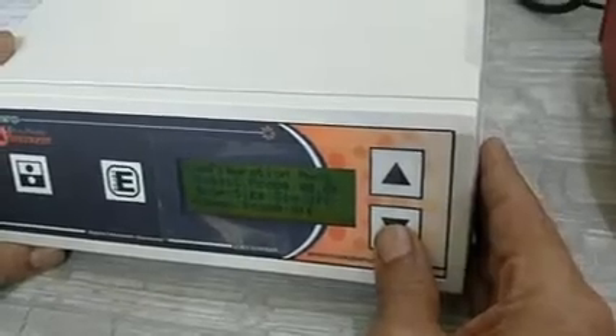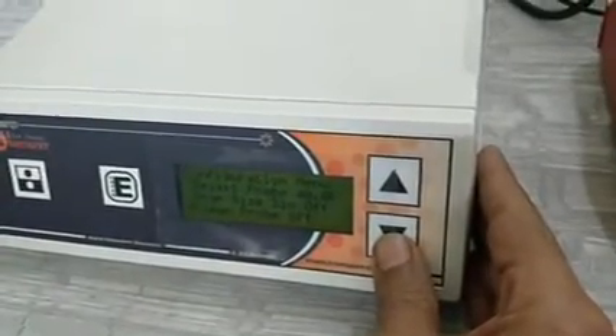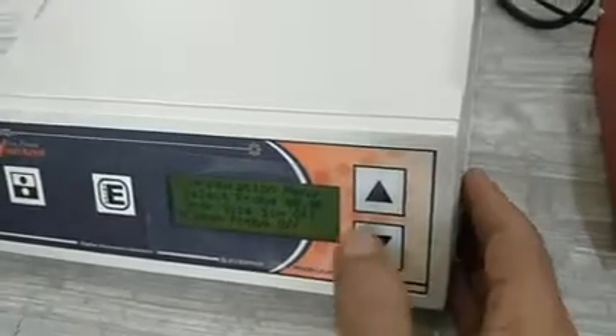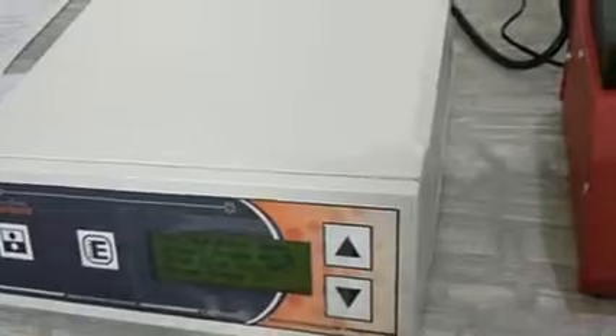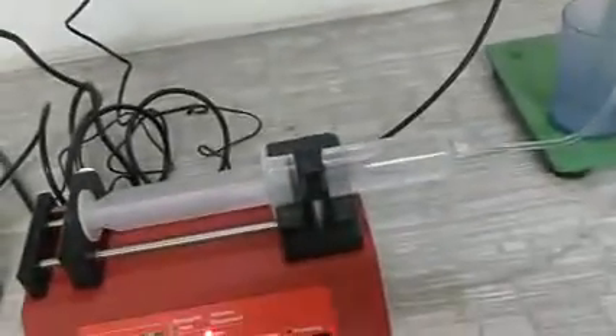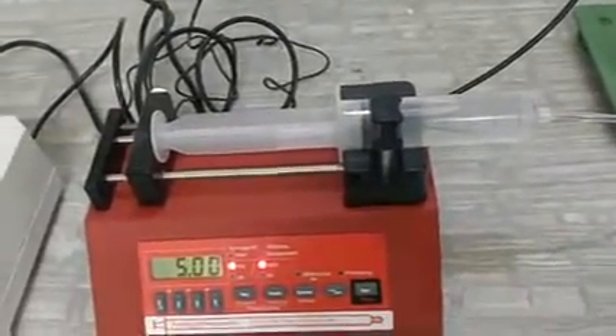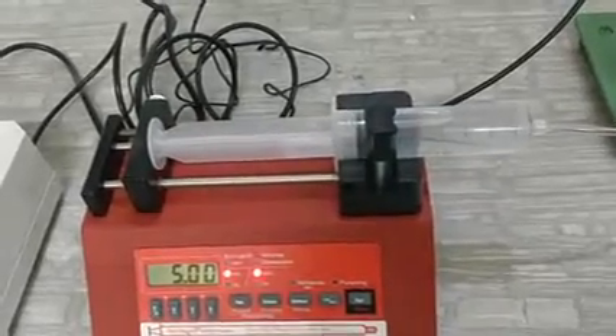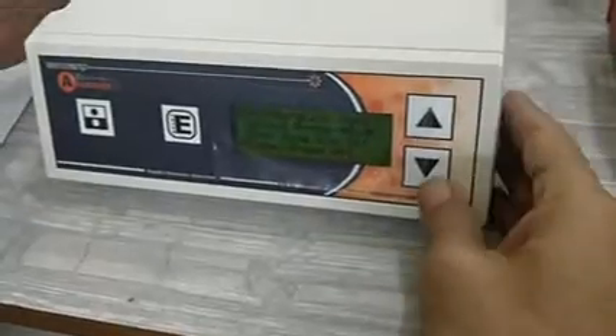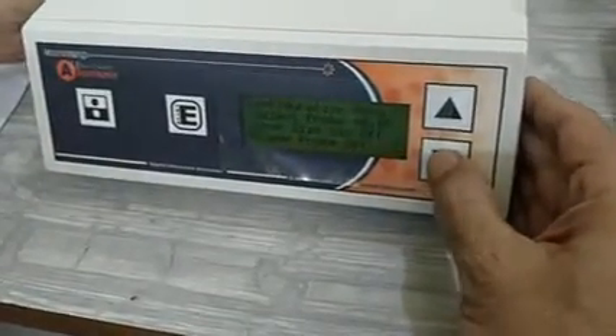Then there's clean probe. Cleaning the probe means, if you put it on, the machine will run for 1 minute, but at that time your syringe should contain a cleaning solvent, like alcohol, acetone, or maybe a soapy solution. Once this is on, cleaning is done for around 1 minute, and if you want to clean a second or third time, you can do that. At this moment we are keeping it off.